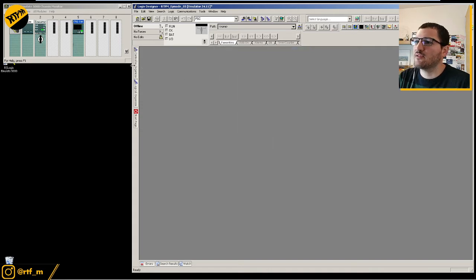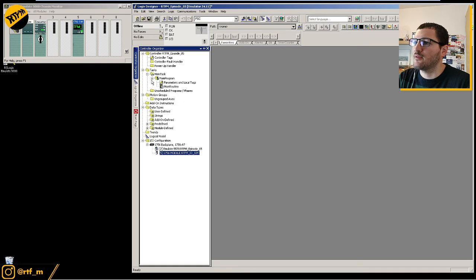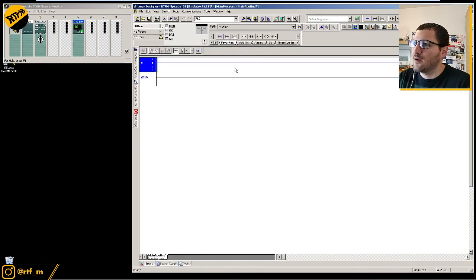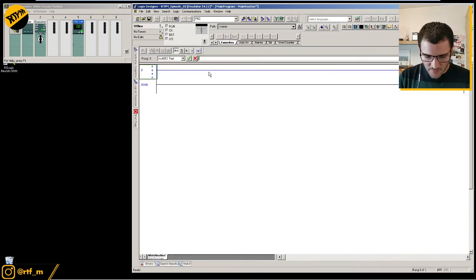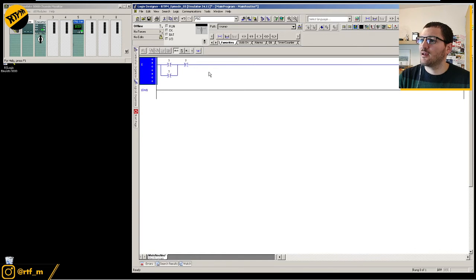So before we download, let's just write a bit of code here so we can simulate that, right? So we're gonna do a BST, branch start, check, normally open. NXB, next branch, is going to be another normally open. BND, branch end, and then a normally closed, OTE. So here we go. We've got a simple start stop.